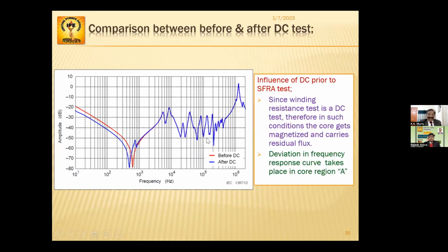Next, as transformer commissioning engineers and people who deal with transformers know, the winding resistance test is nothing but a DC test. When you take the winding resistance test, the core gets magnetized. So the deviation will definitely be there before and after the DC test. When you take the SFRA before the winding resistance test and after the winding resistance test, there will be a definite difference seen in the core area. That is, this core area is up to 2 kilohertz. This is the core area, so here you can see the difference.